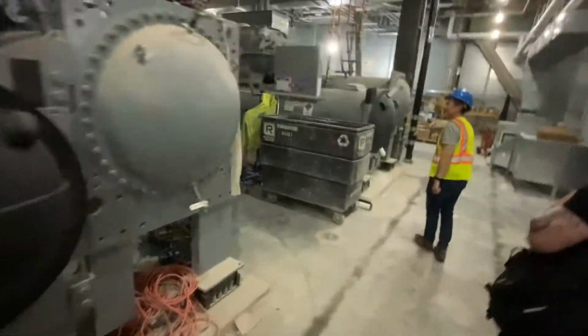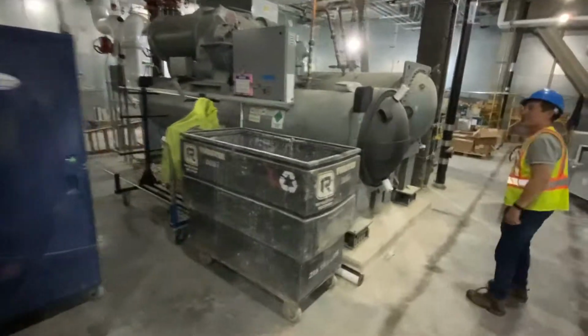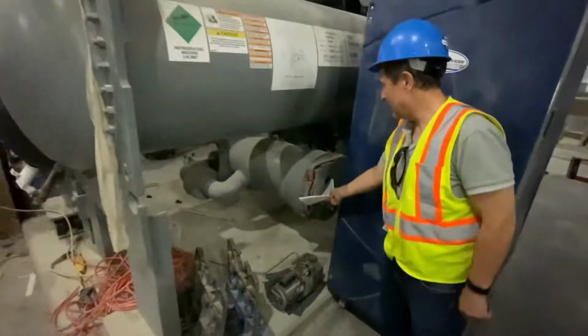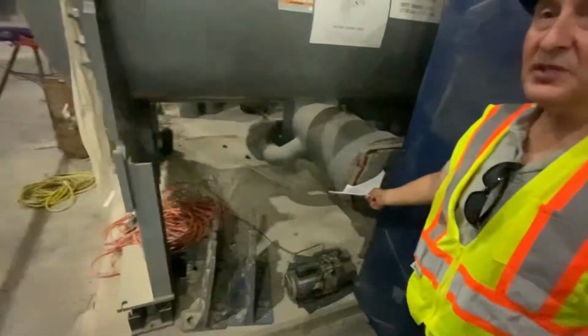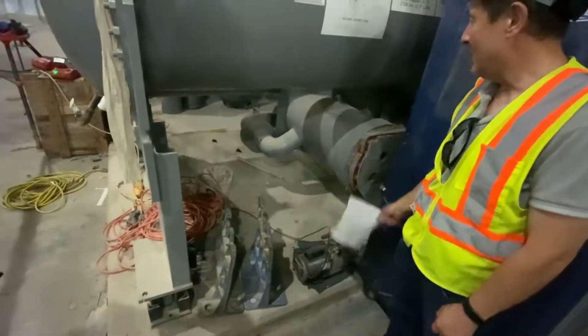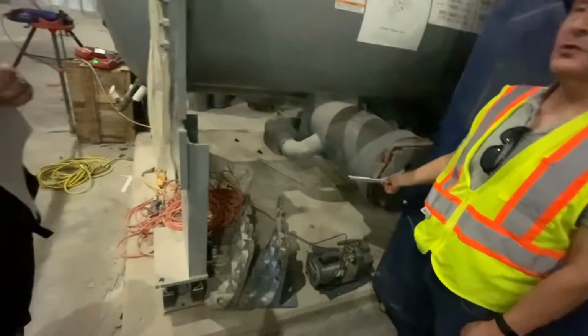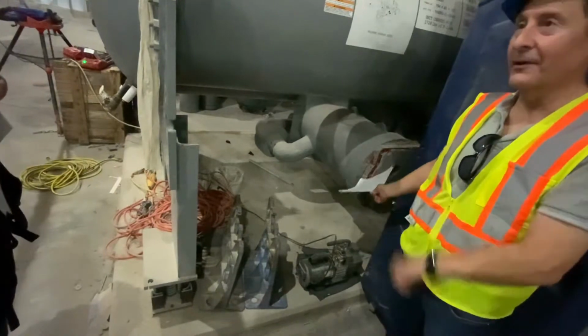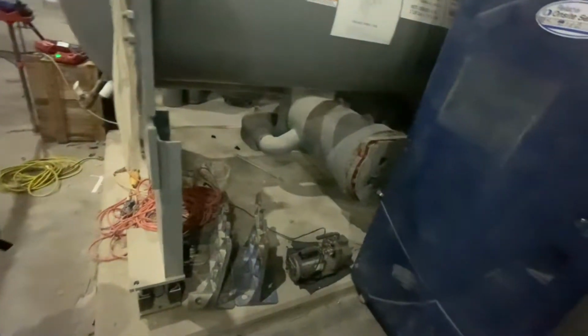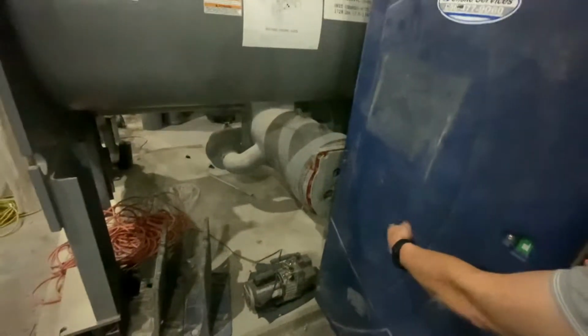There's nothing on the chiller, VFD. We have a two-stage compressor, so because of that, we have an interstage economizer. This is where the interstage economizer float is. There's actually a refrigerant float in there. We walk around to this. You can actually see the refrigerant boiling in those windows if you look in there.